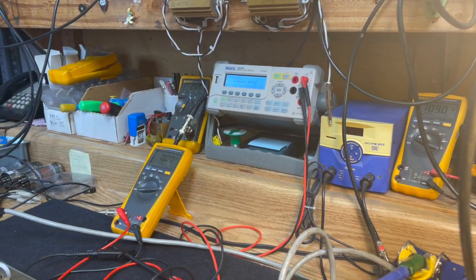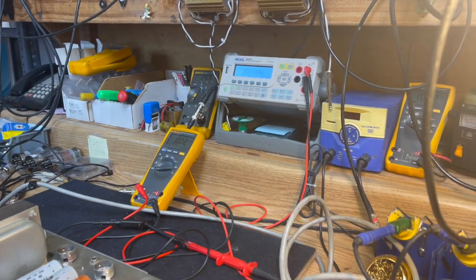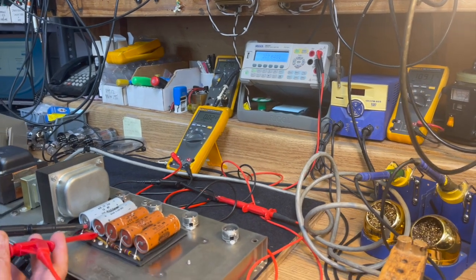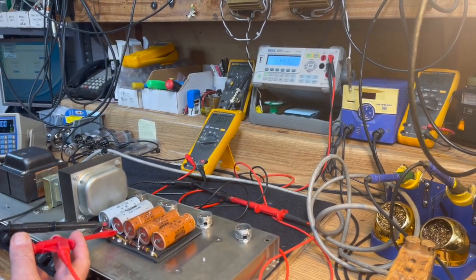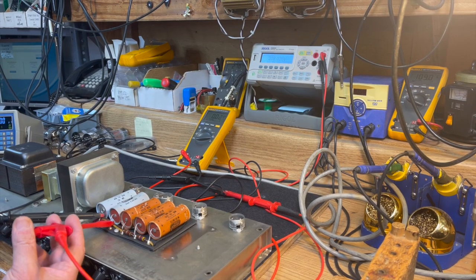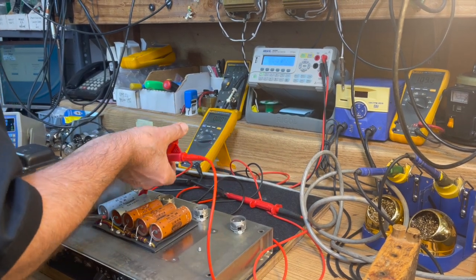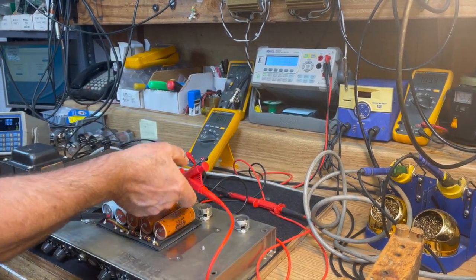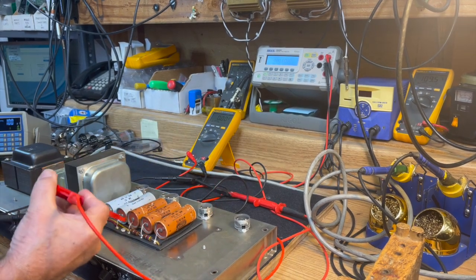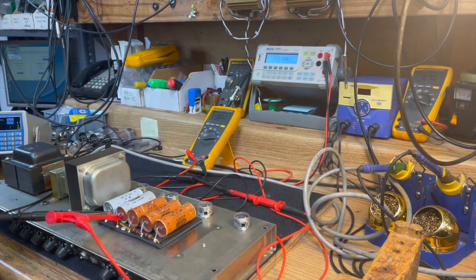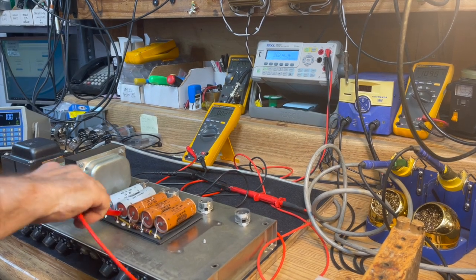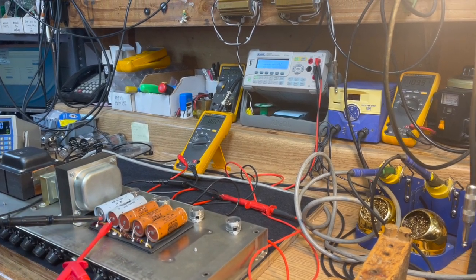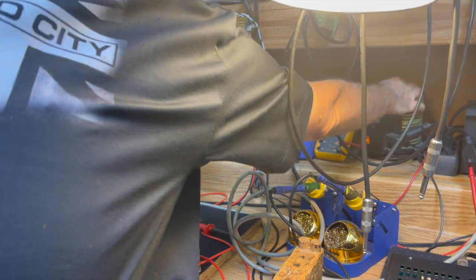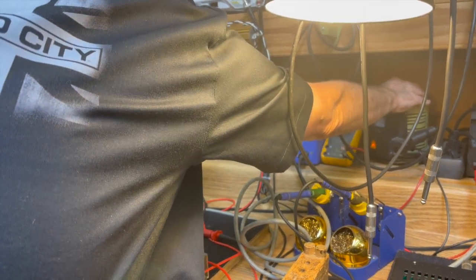So we've got 2 milliamps of leakage current here right now of these two capacitors in series. I'm going to go here, just measuring one of them, we're at 1 milliamp, which again is nothing. So let's go up to 250. I'm just going to keep stepping it up like this until I see significant movement on the meter, on the amp meter.